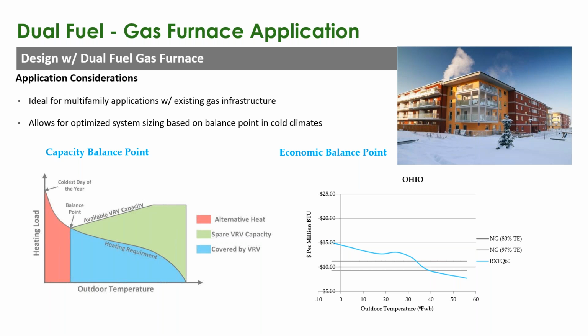In this scenario, the heating requirement would be covered by the variable refrigerant system for the majority of the time. And once you got to your balance point, everything would switch over and gas heat would run to the coldest day of the year and then switch back over once it got above balance point.